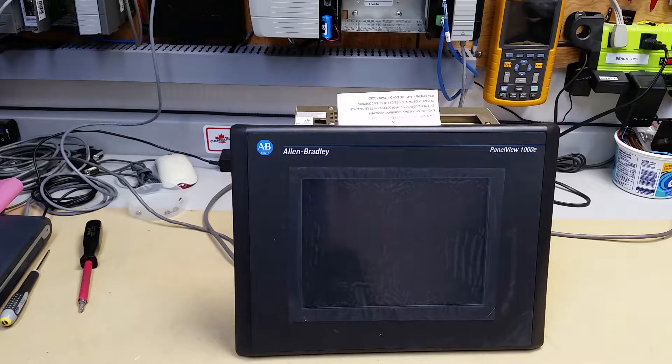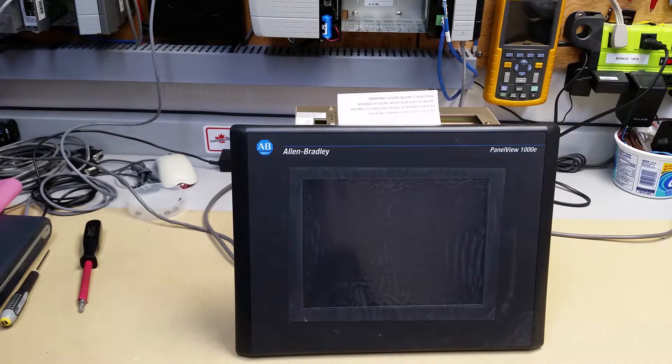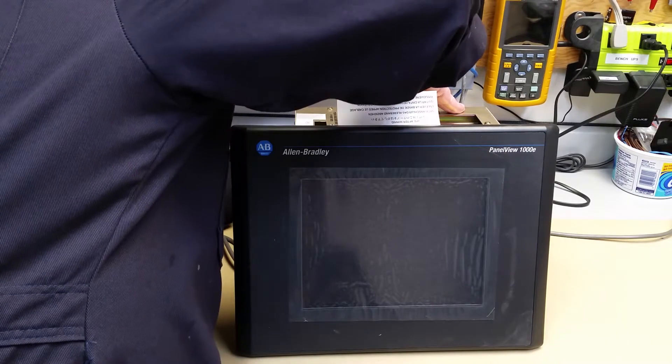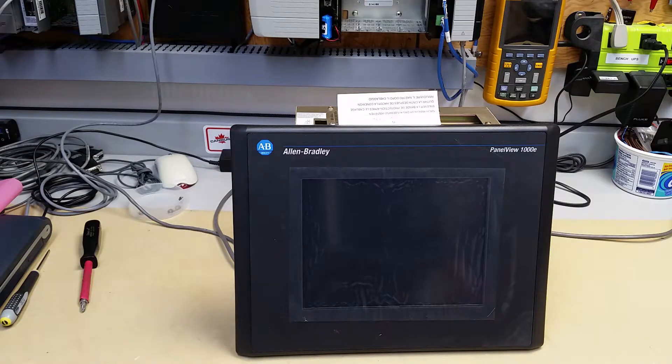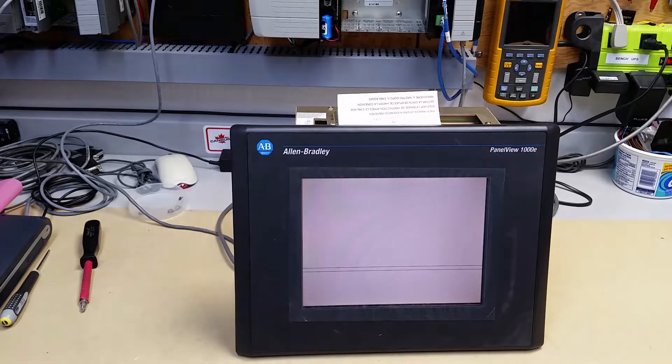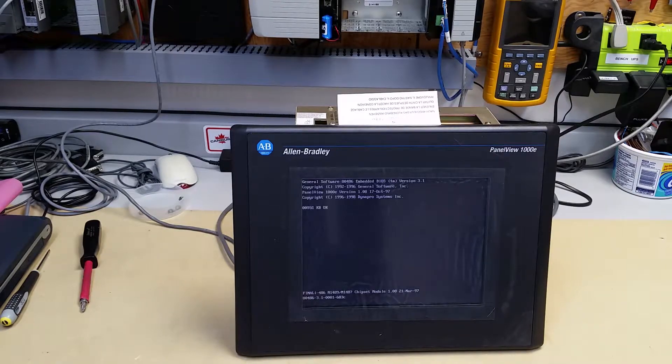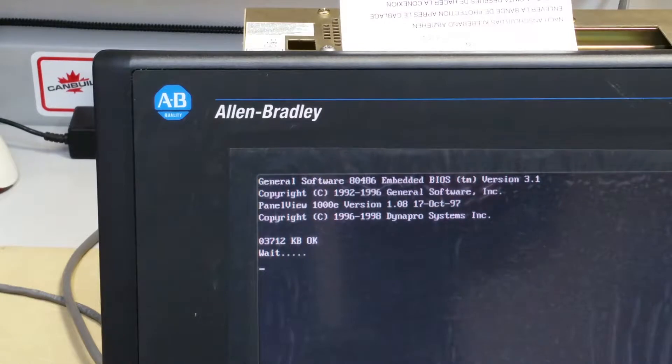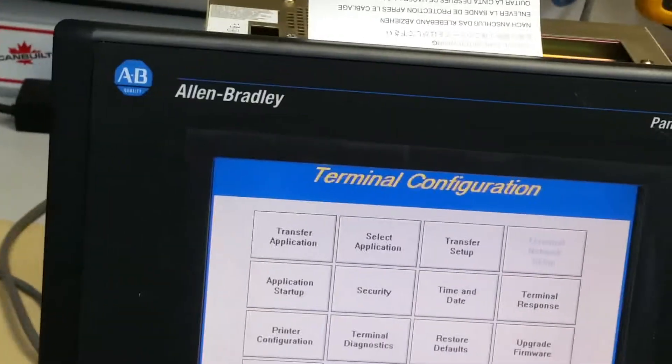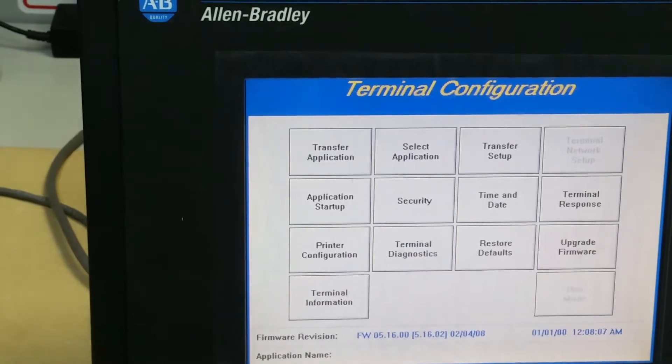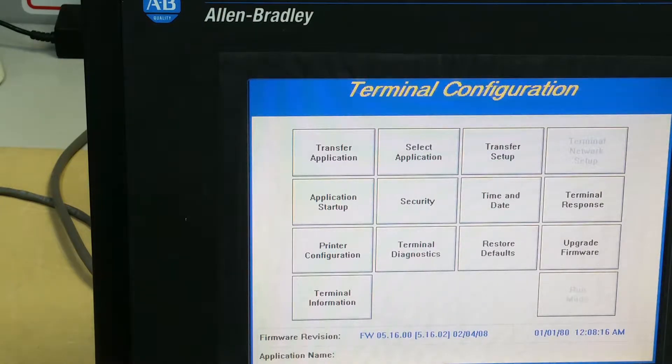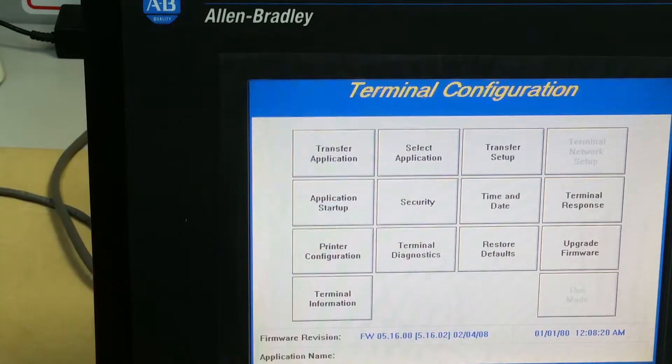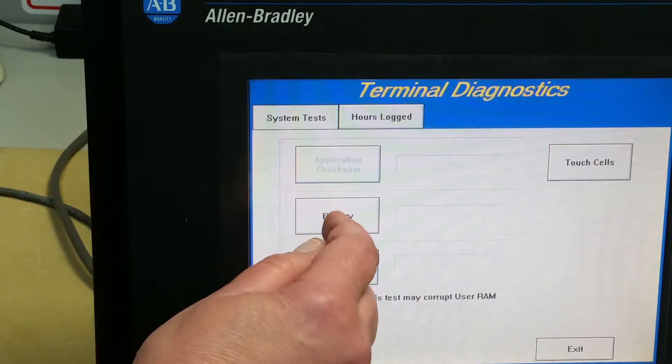We're ready to power it up. I've got the back off of it still. I've got the key switch on it and put the key in because once we get it powered up we have to load an application. Power it up and it's going to go through its startup, making all kinds of funny little noises. As you can see on the bottom, our date is 1980, there's our firmware. Now the reason we went through all this was the battery was dead. Hit battery and it passes now with a new battery in.